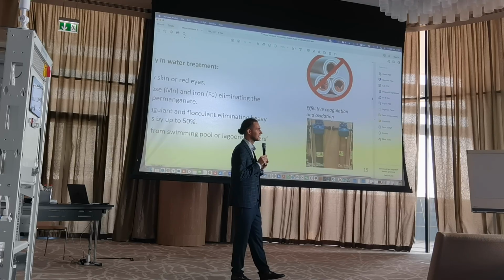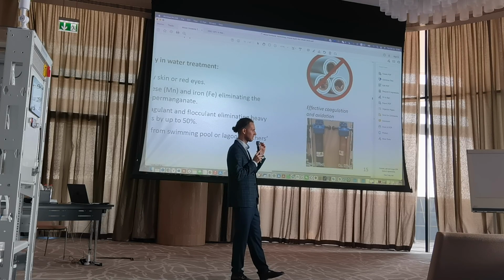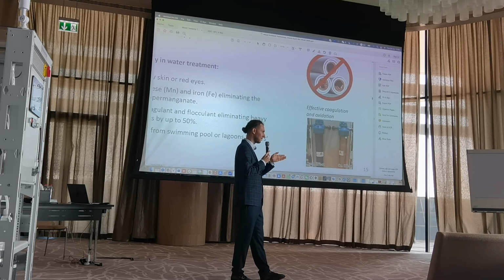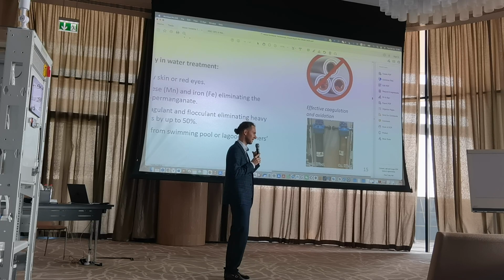Because the problem is with biofilms, and the microbes are under the biofilms. Biofilms are like an independent city - they have their borders, their guards who protect those living inside, and they accumulate on the internal surfaces of pipes and tanks. It's very difficult to oxidize. Hypochlorous acid has the ability to penetrate through this wall in the biofilm.